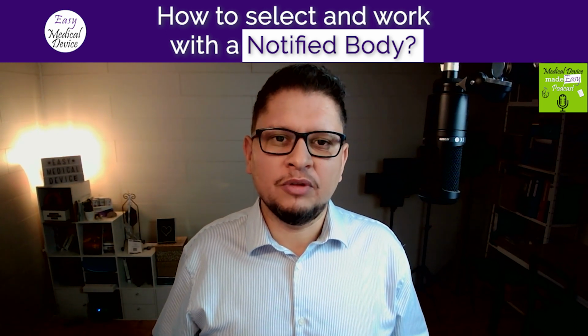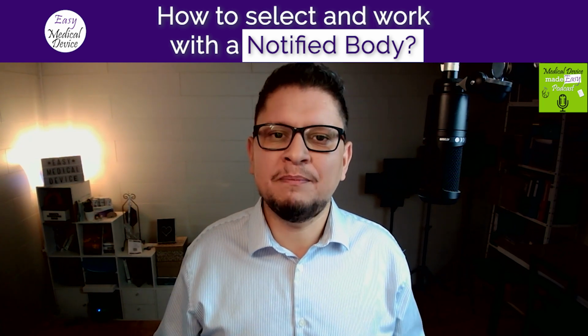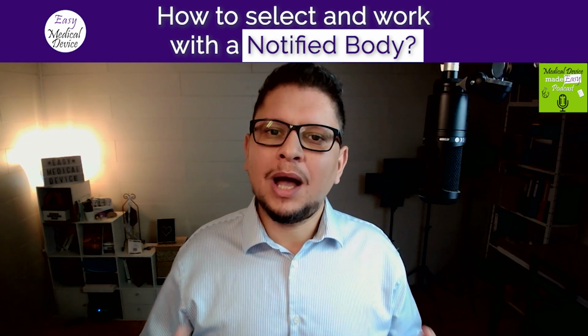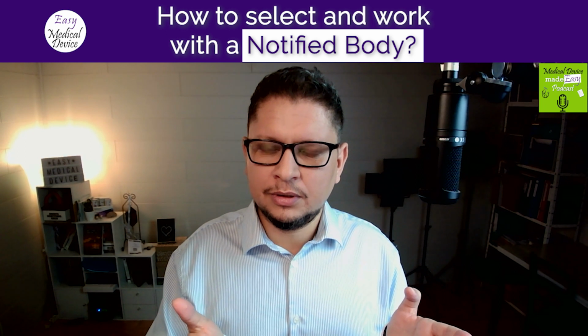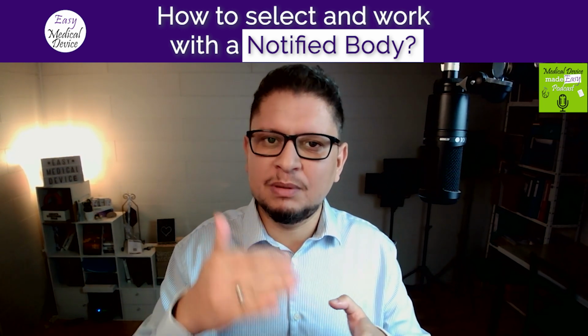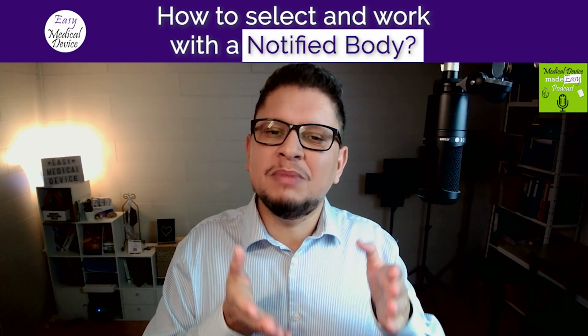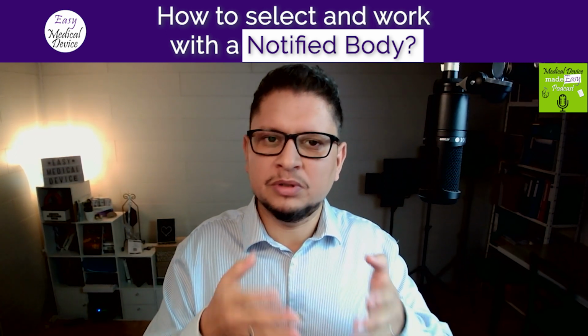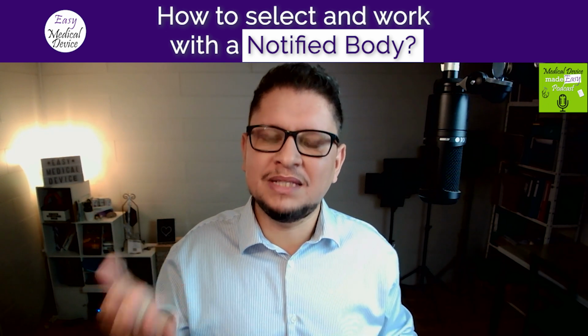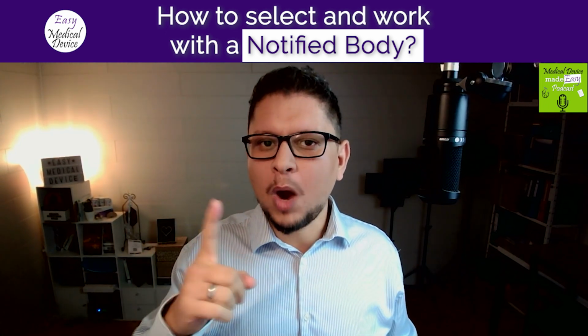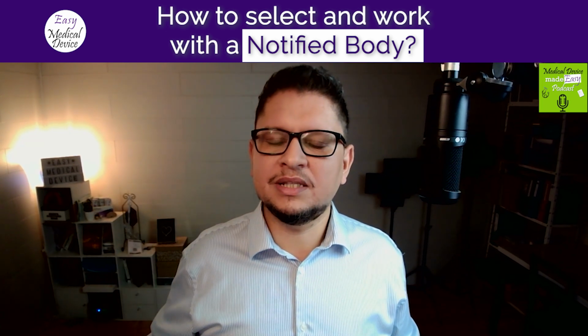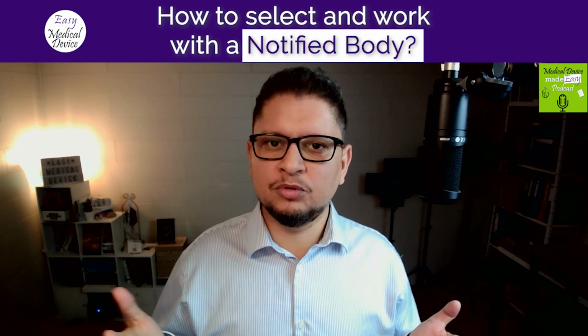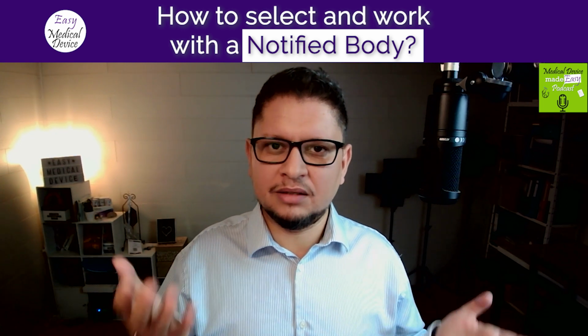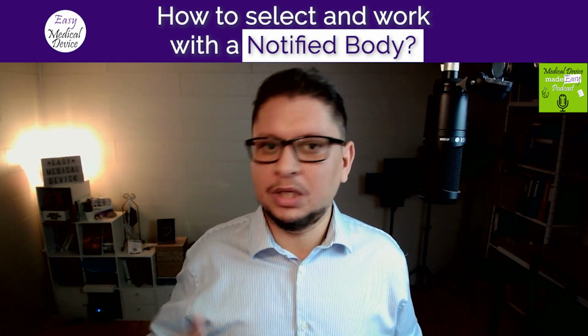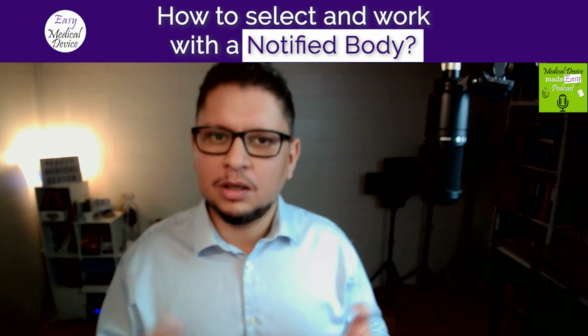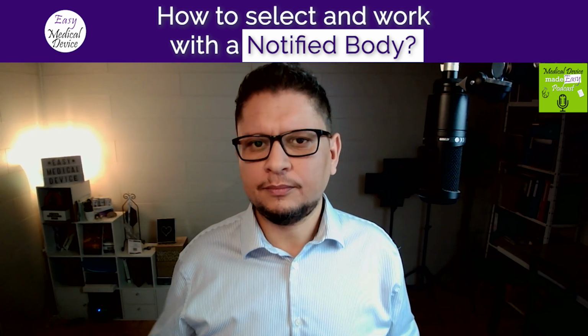This list will also be important for them, because they should do a sampling of your devices. What does it mean? It means that if you have multiple class 2A products under the same MDR codes, multiple products also mean multiple technical files, not only one. If you have one technical file with all the products, it's not the case. It's multiple technical files under the same MDR codes for class 2A. Then they can sample one product for this list of class 2A MDR codes. So if you have 10 products with the same MDR codes under class 2A, which have 10 technical files, they will take only one and review only one. They assume that if the one they reviewed is conform, all the others should be conform. So it's the sampling method.